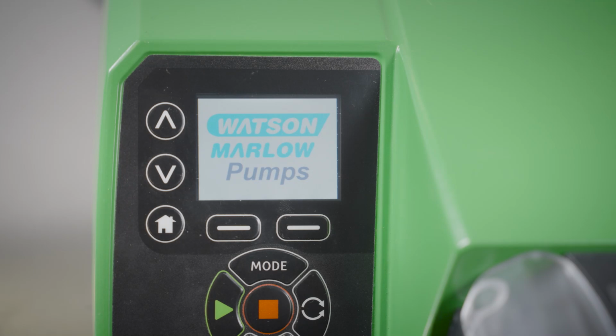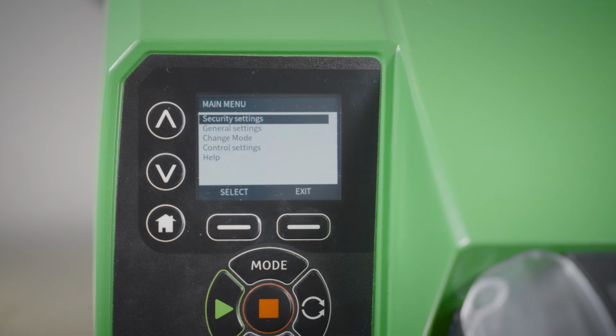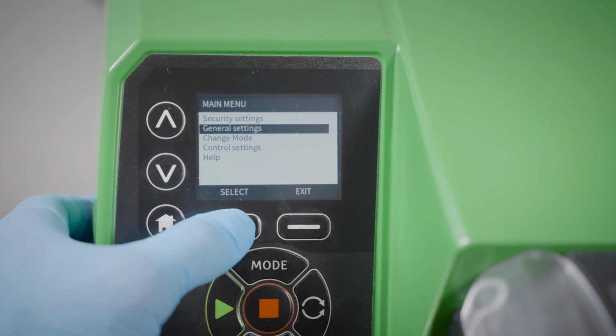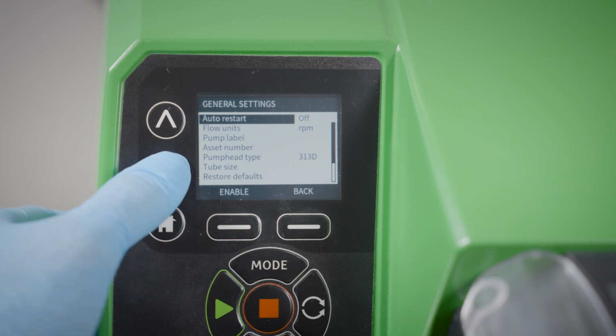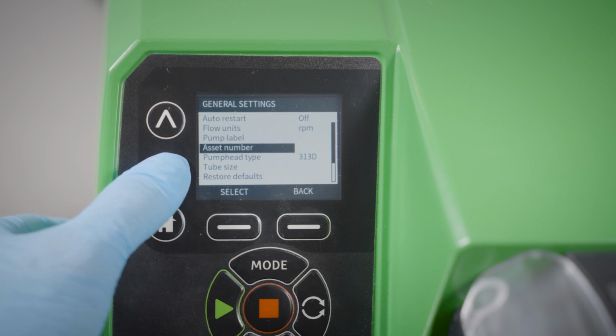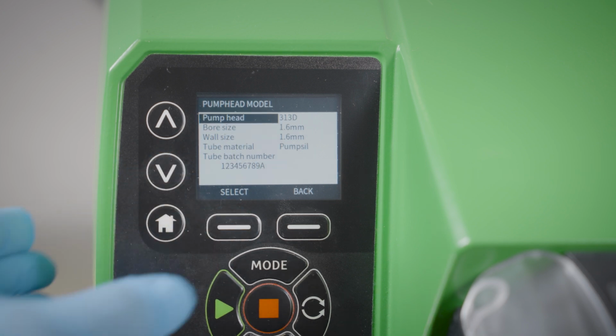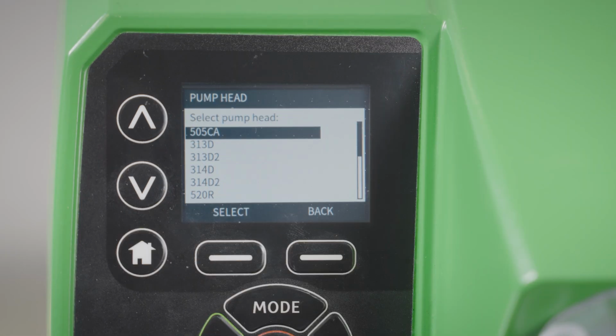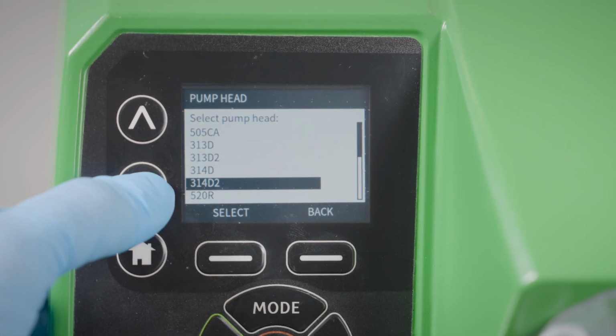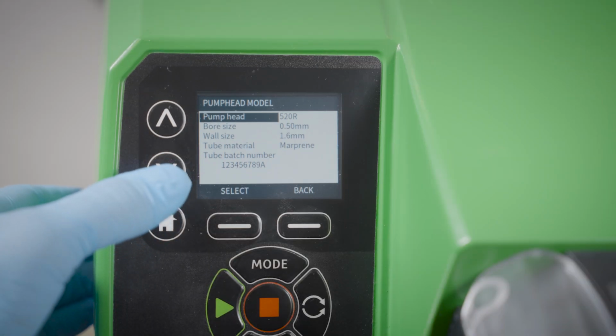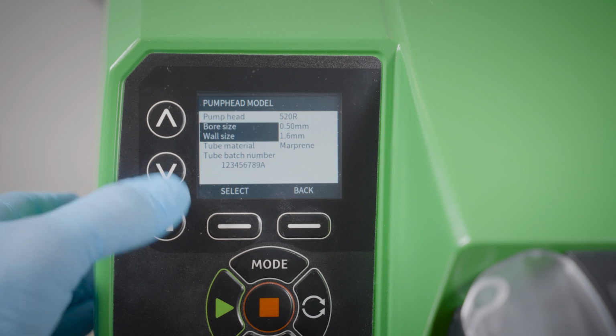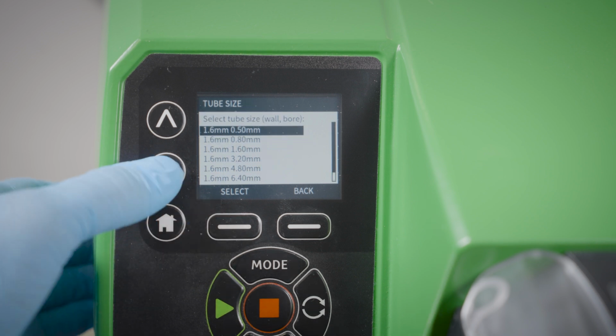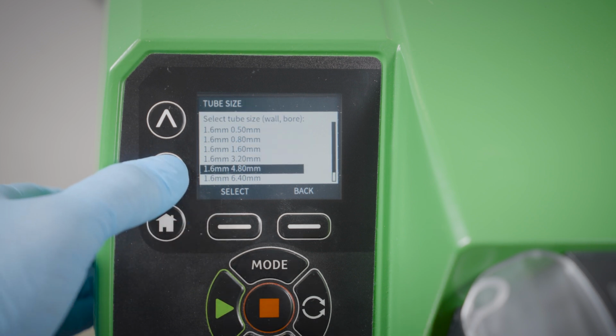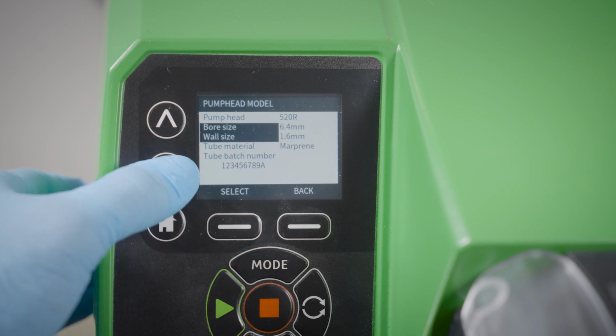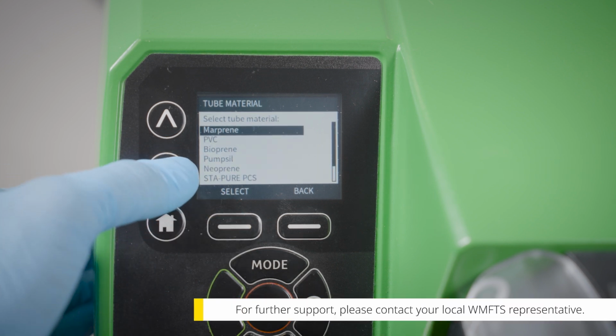We'll need to configure and calibrate the pump. Navigate to Menu. Navigate to General Settings. Select pump head type. Select your pump head. Navigate to tube size and select it. Navigate to material. Select material and return home.